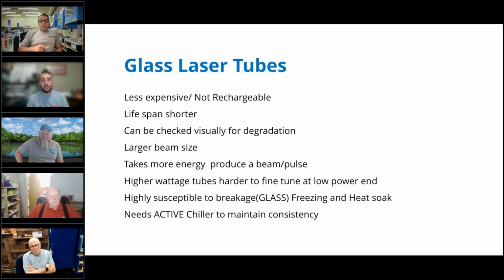And also very reliant on your ambient temperature for how well it can cool. Even fan cooled RFs are susceptible to it. And then your chiller, even with the active chiller, if you're in what they call intelligent mode that floats with the ambient temperature, so like I'm in a garage and in the morning it may be 60, by the afternoon it could be 85. If I was in intelligent mode, the chiller might float with that versus keeping it in the constant mode where I tell it, hover around 20 degrees Celsius no matter what the ambient is as best you can. So just from a variability standpoint.